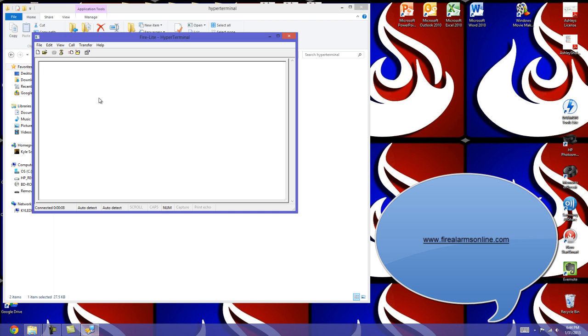tied from your COM port to the fire control panel, if you press enter on your keyboard, you should get the display to appear here in this box. And once again, HyperTerminal is a useful tool for capturing information off the panel, whether it be pulling a loop off to find out what devices are currently installed in the system, or capturing text for a test.